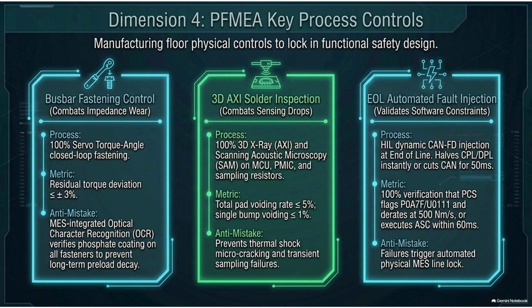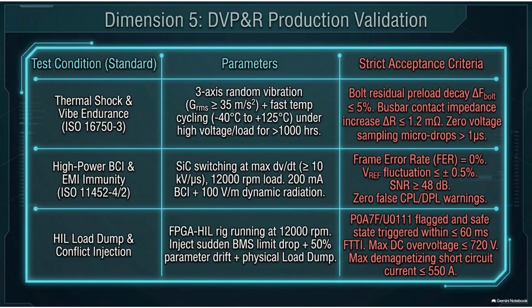What are the engineering pass-fail metrics after the 1,000 hours are up? They can't just look at it and say, yep, it works. No. They tear the unit down completely and measure the physical degradation. Those torque angle bus bar bolts we talked about cannot have lost more than 5% of their initial clamping force. Wow. Furthermore, they measure the contact resistance across the high-voltage joints. The resistance cannot have increased by more than 1.2 milliohms from its pre-test baseline. 1.2 thousandths of an ohm is the maximum allowable degradation after 1,000 hours of torture. The tolerances are microscopic. They have to be.